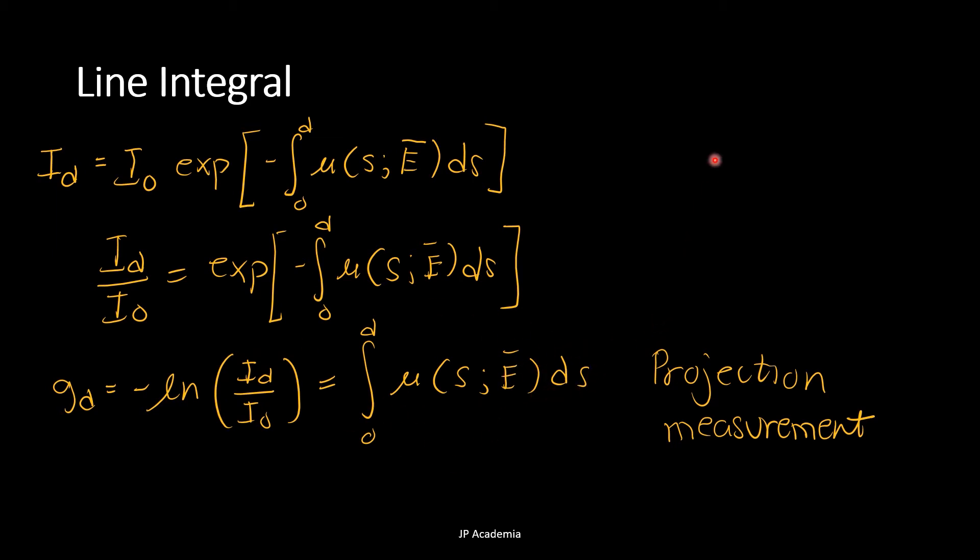With this, we can see that the basic measurement of CT is a line integral of the linear attenuation coefficient at this effective energy. This reference intensity I sub naught is measured for all the detector elements during the calibration step of the machine. This is commonly called the air calibration, done usually in the morning.